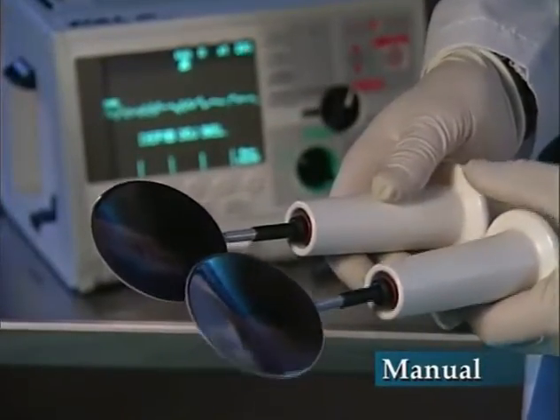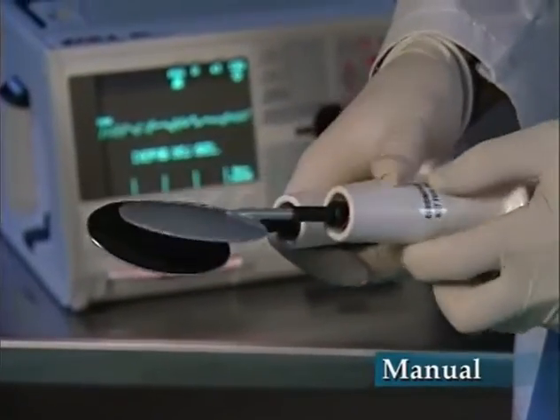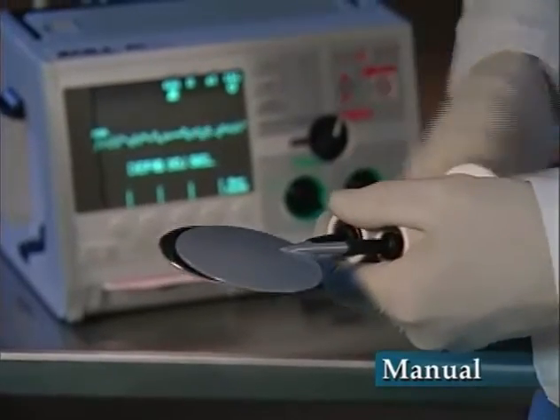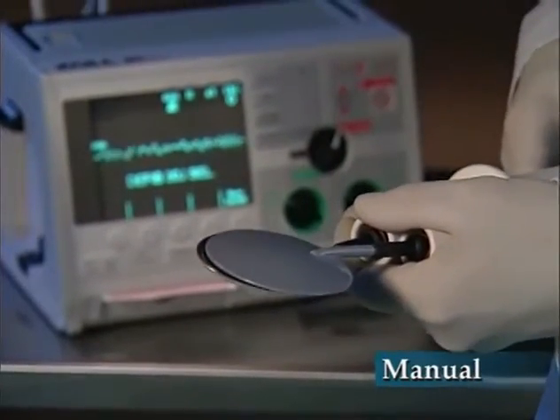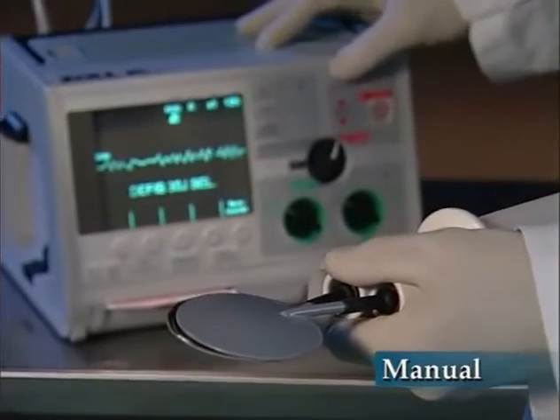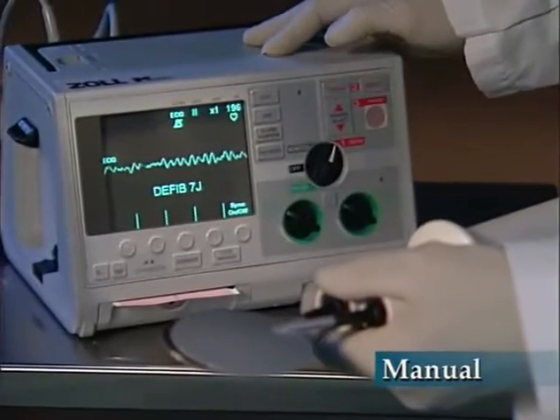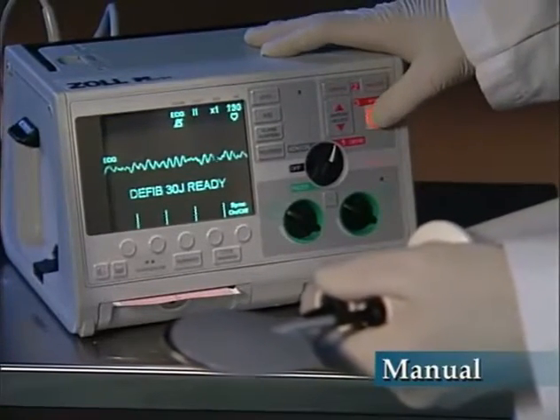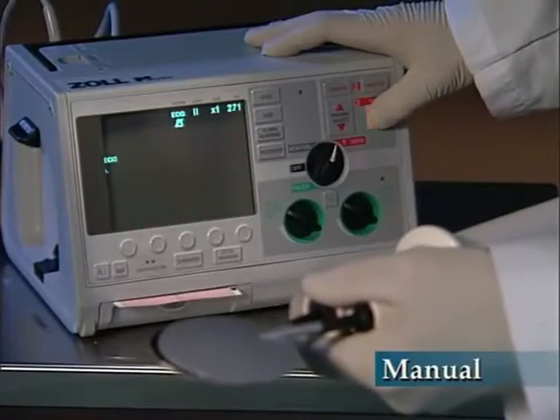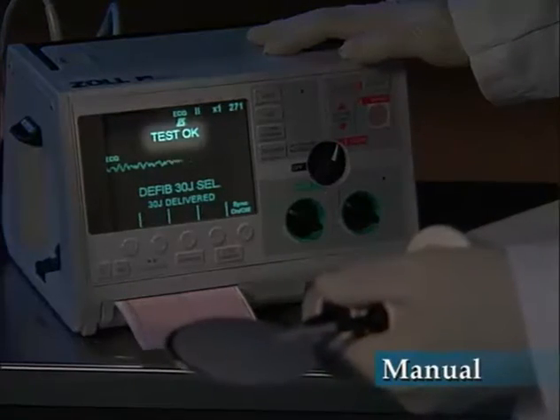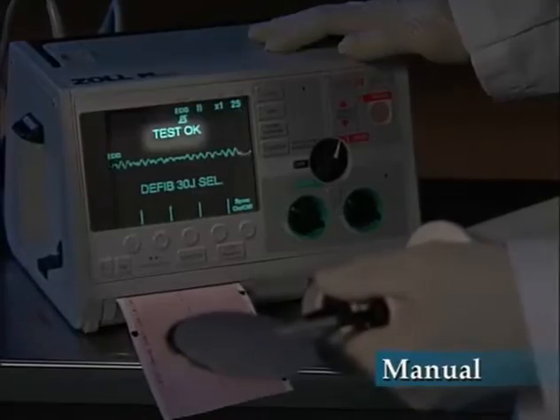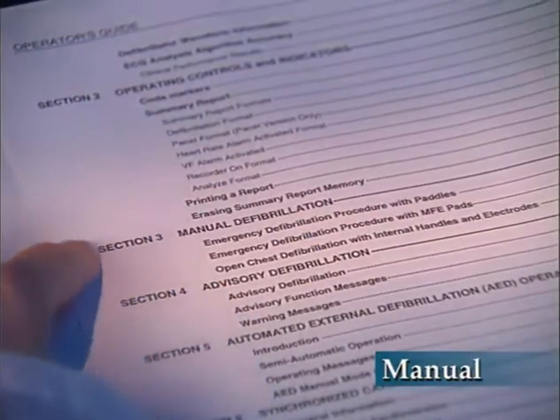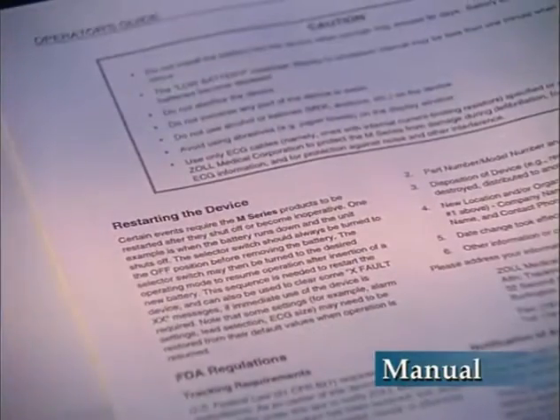To test your internal paddles, simply place both paddle surfaces together, keeping your hands off of the electrodes. Charge the device to 30 joules, press the shock button, and note the Test OK message that appears to indicate energy has been delivered to the assembly. Complete information on internal paddles, including procedures for cleaning and sterilization, is available in your operator's guide.